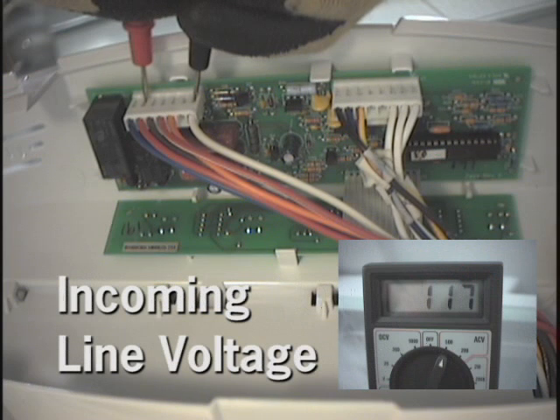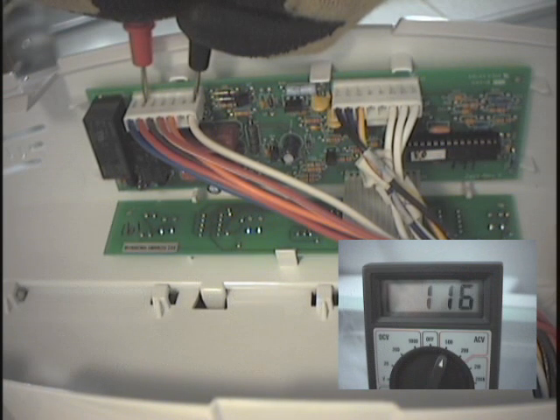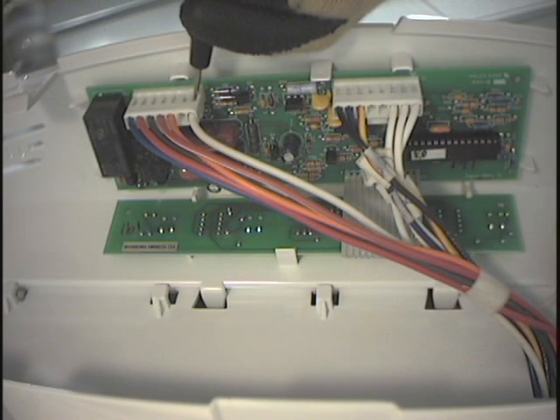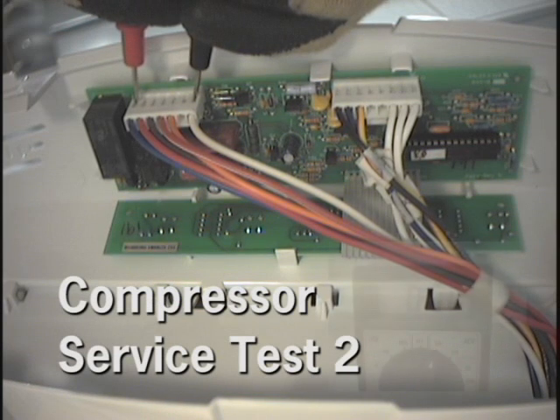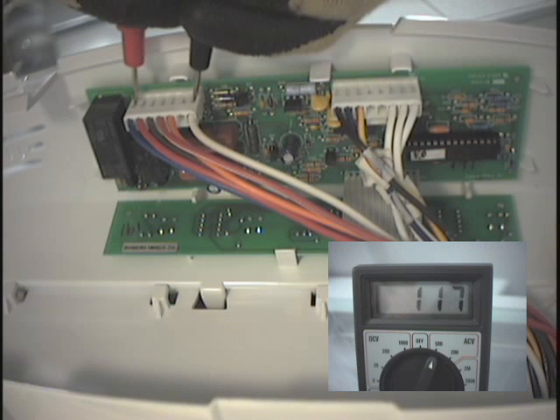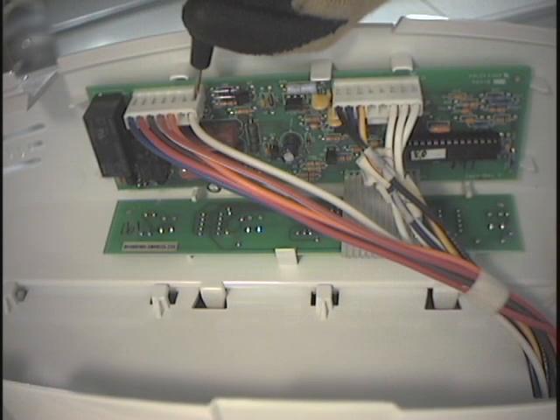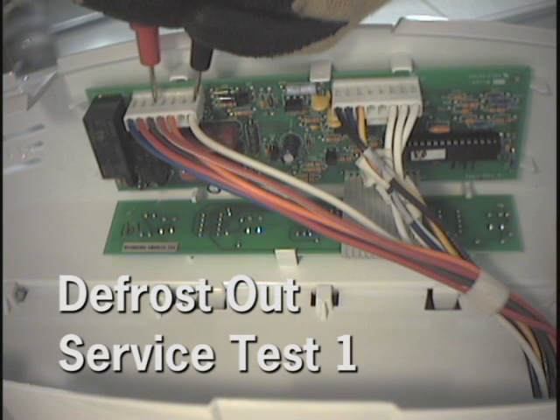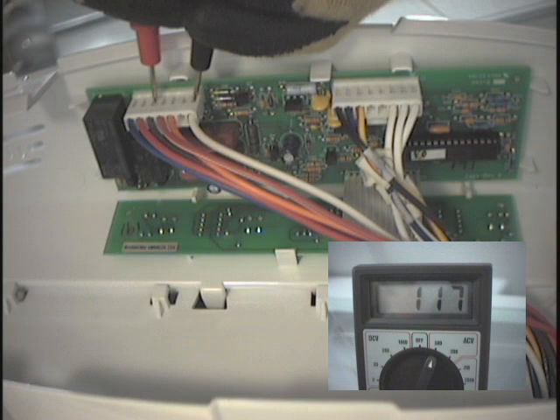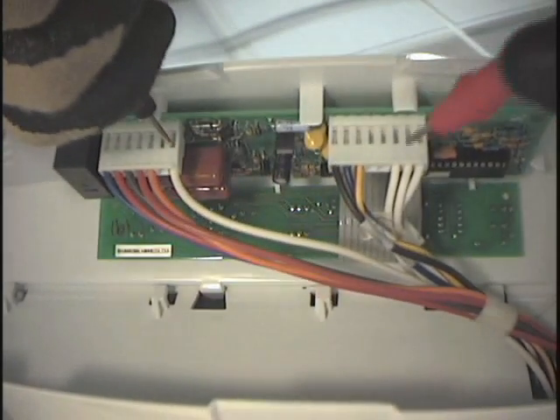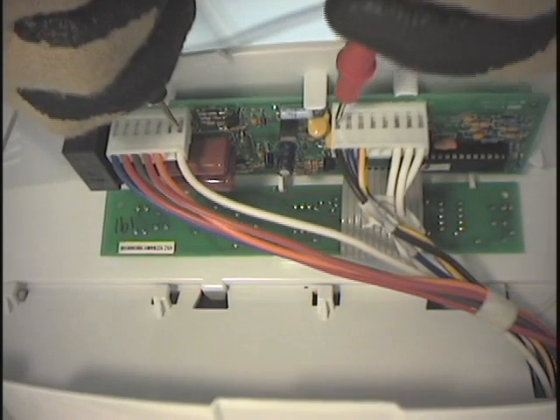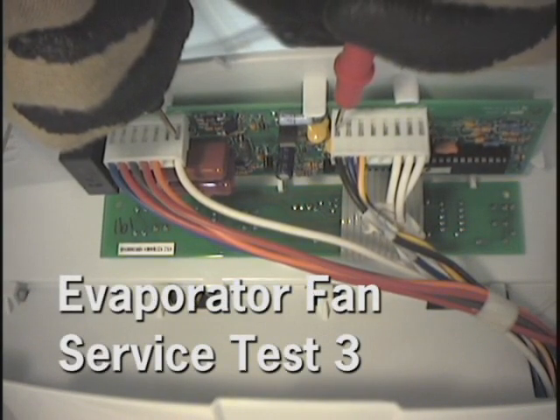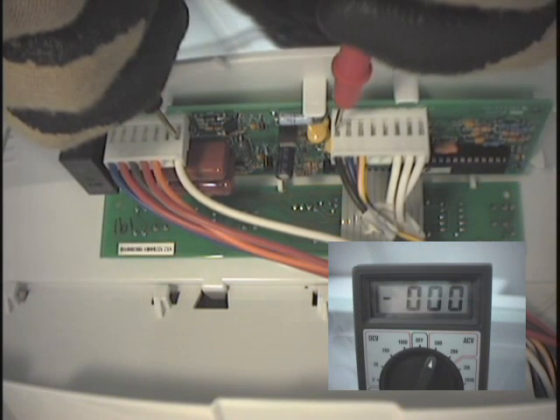The supply to the control should be line voltage. When powered, the compressor voltage should be line voltage. The defrost circuit output is also 120 volts AC. The evaporator fan and the damper motor are switched on the neutral side. When energized, the voltage should go to 0.